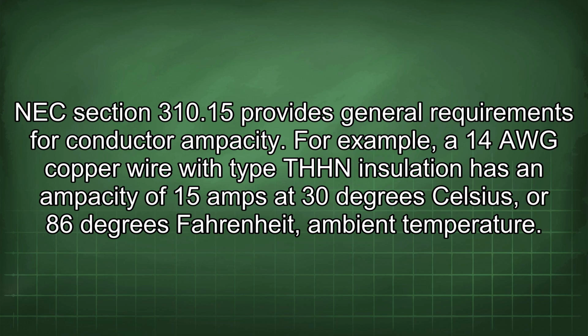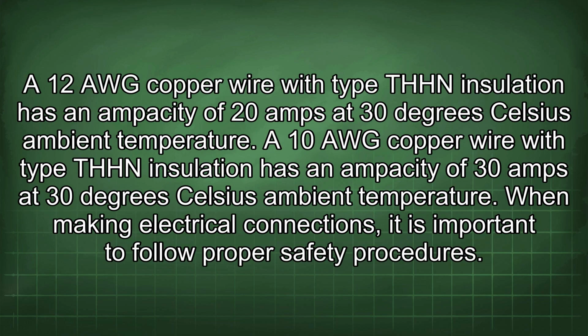For example, a 14 AWG copper wire with type THHN insulation has an ampacity of 15 amps at 30 degrees Celsius or 86 degrees Fahrenheit ambient temperature. A 12 AWG copper wire with type THHN insulation has an ampacity of 20 amps at 30 degrees Celsius ambient temperature. A 10 AWG copper wire with type THHN insulation has an ampacity of 30 amps at 30 degrees Celsius ambient temperature. When making electrical connections, it is important to follow proper safety procedures.